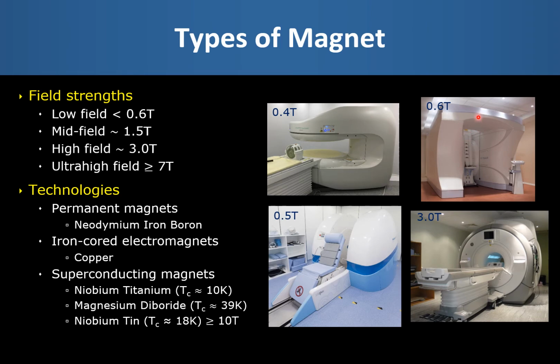There are very few iron cored electromagnets around. The example here is actually a 0.6 Tesla system developed by Raymond Damadian's company Fonar that is called the stand-up MRI. This system is particularly useful for looking at loaded joints or joints where pain may only occur in certain positions that could not be achieved in conventional cylindrical superconducting magnets. In this case, the magnetic field is horizontal. The downside is that the iron former here weighs approximately 111,000 kilograms, and it requires a 100 kVA power supply and an additional 47 kVA power supply just for the water chiller to dissipate the heat generated in the windings.